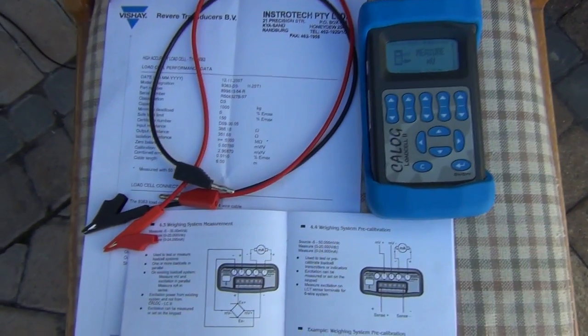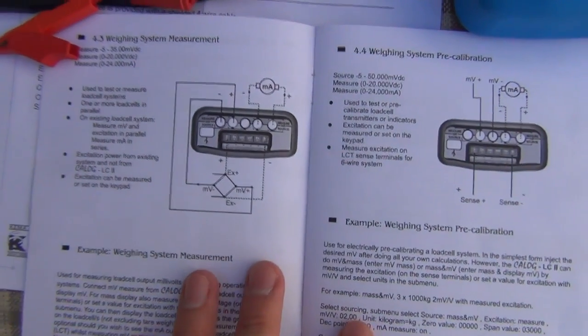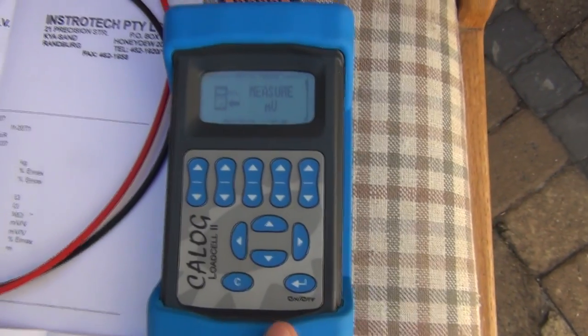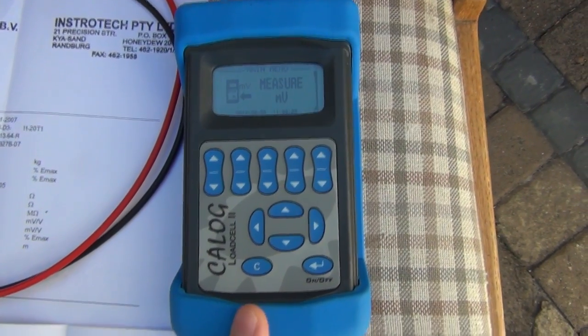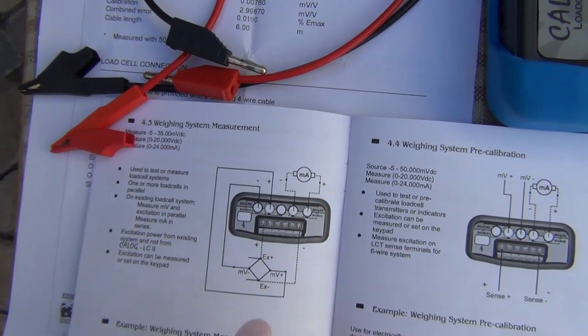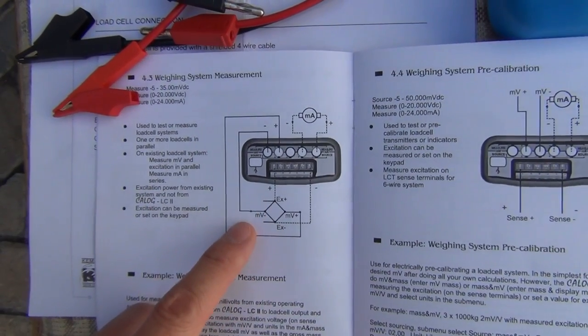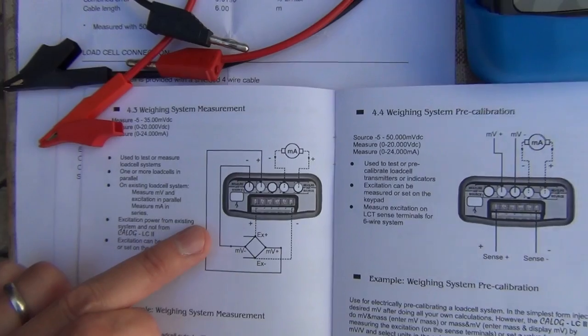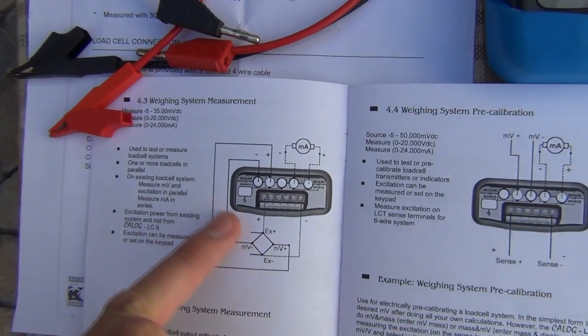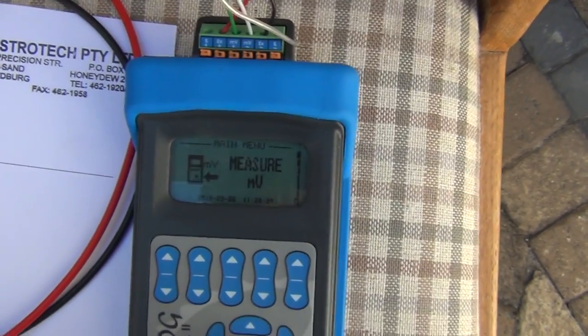There are a couple of tests I can't demonstrate here that can be done with this device. One is to check the weighing system itself — the CALOG Loadcell II acts as a millivolt measurement from the output of the load cell, using the excitation voltage from the load cell transmitter. You can measure the millivolt output from the load cell, the milliamp output from the transmitter, and also check that your excitation voltage is correct. I'll show what that looks like on the display itself.